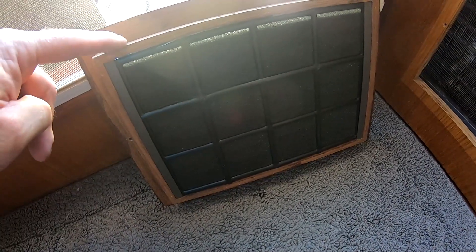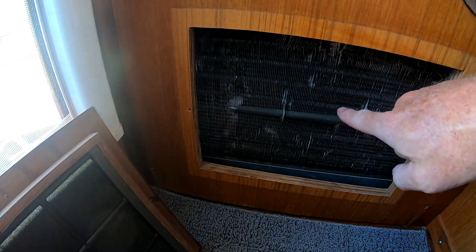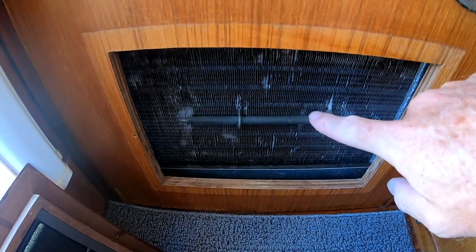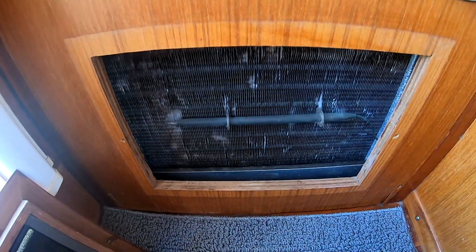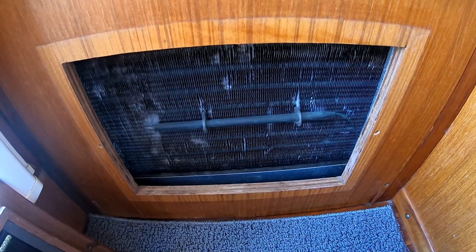I was missing two of these filters, so that's what I did yesterday. Now air goes across that condenser — it comes through this hole right here, the dust collects onto this filter, then the air comes back out up to the top. If this is all plugged up, you can see where that could cause a problem. Anyway, I ended up cleaning all the fans and adding two of these filters to the system.